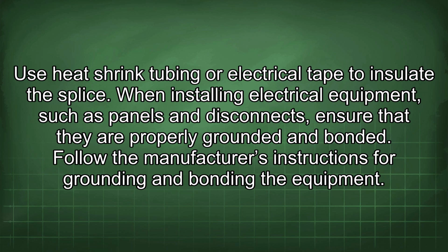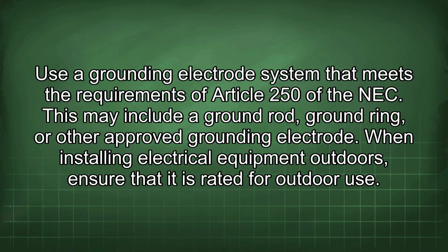When installing electrical equipment, such as panels and disconnects, ensure that they are properly grounded and bonded. Follow the manufacturer's instructions for grounding and bonding the equipment. Use a grounding electrode system that meets the requirements of Article 250 of the NEC. This may include a ground rod, ground ring, or other approved grounding electrode.